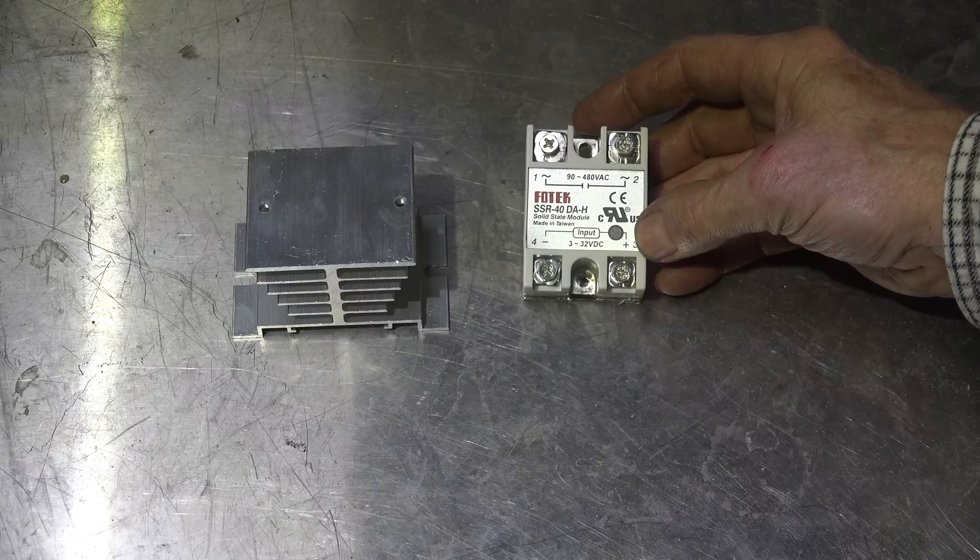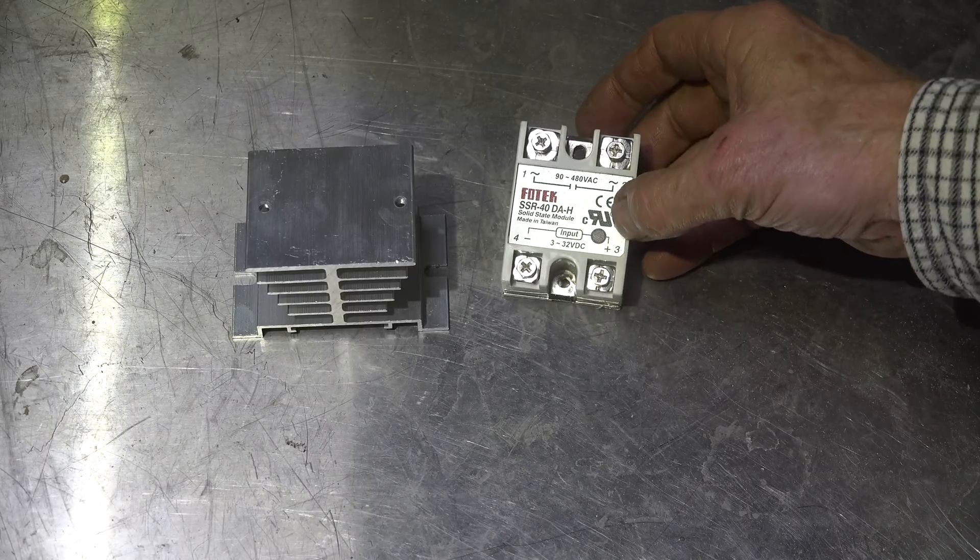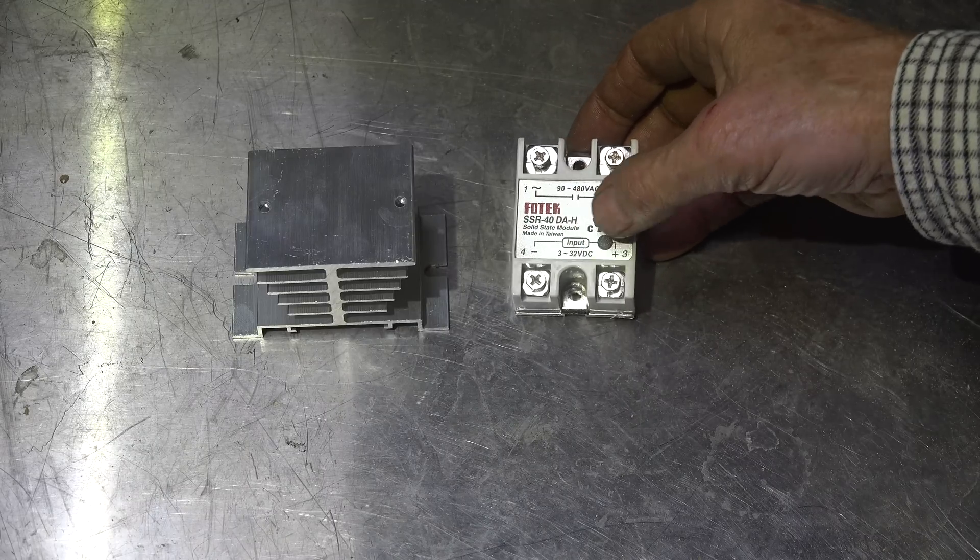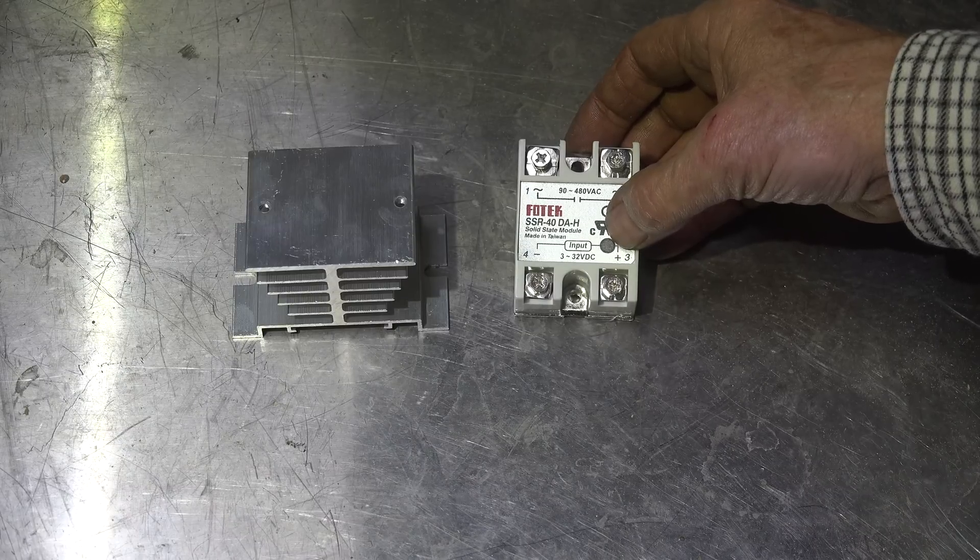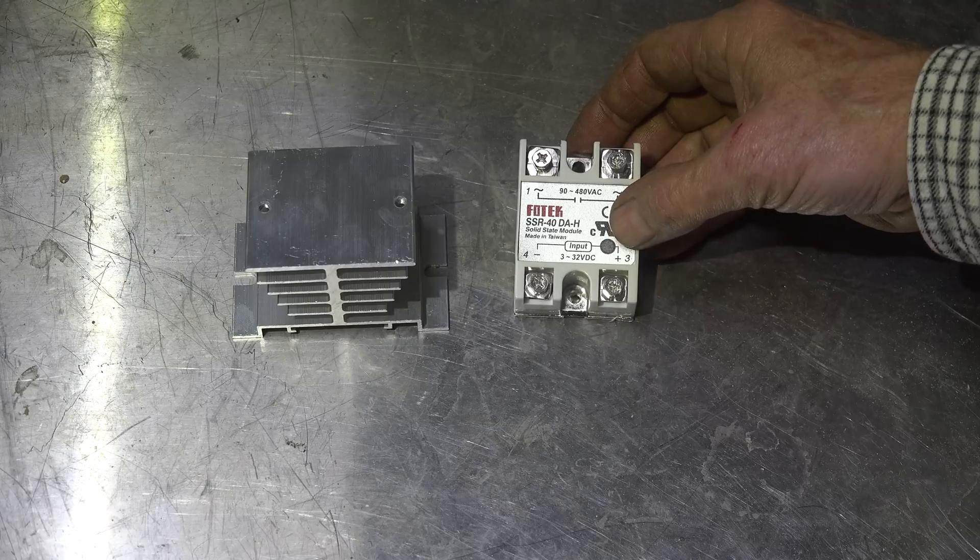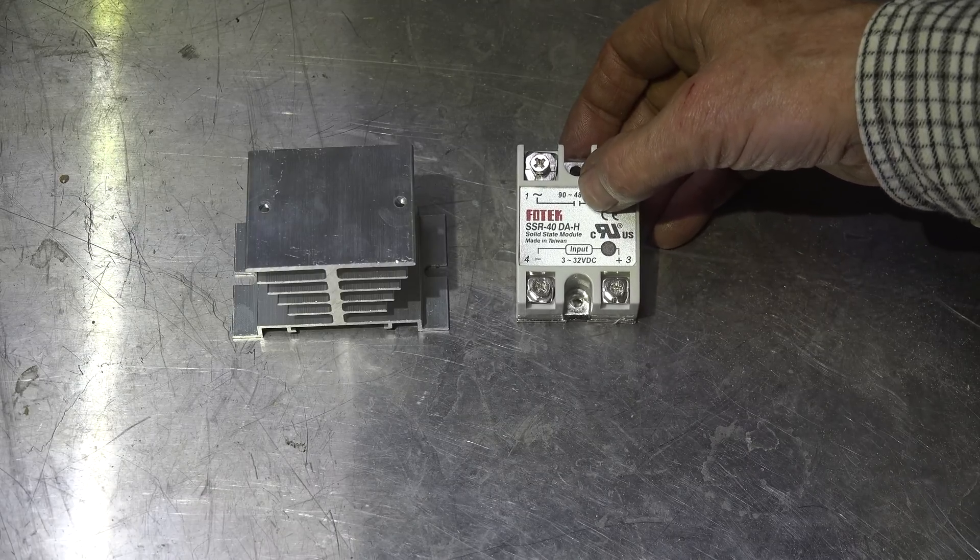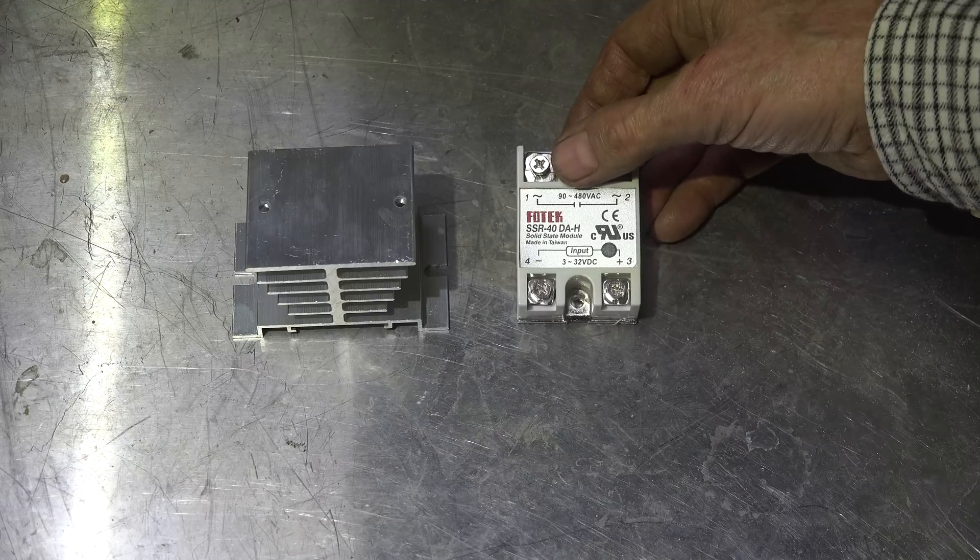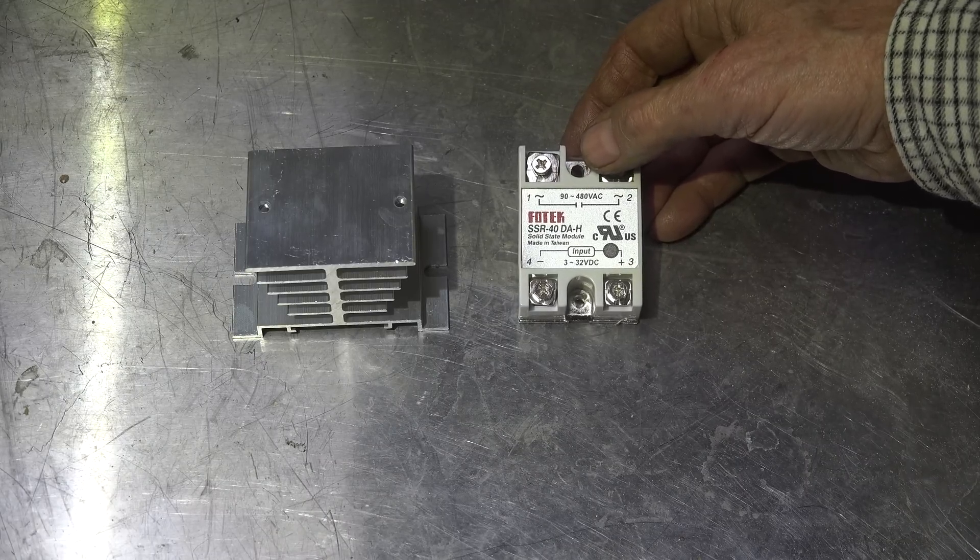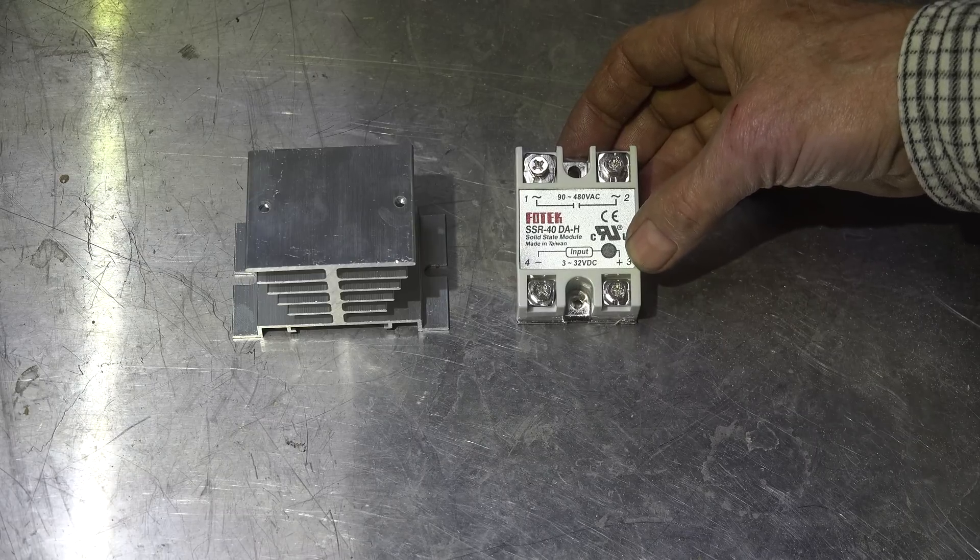A couple other things about this: you can run DC into this and it will energize. That little light right there will come on. If I put power into this thing, it will energize anywhere from 3 to 32 volts DC, and it will close a set of normally open contacts here from 90 to 480 volts AC. Like I said, it will handle 40 amps.